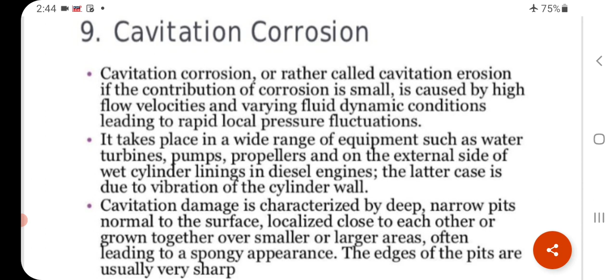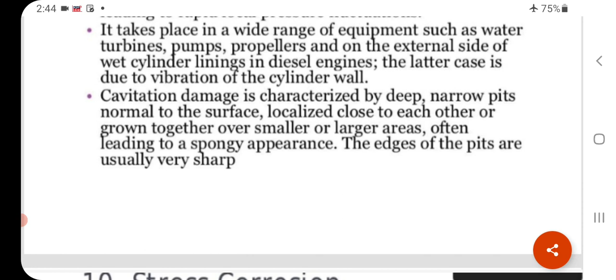Cavitation corrosion, or rather called cavitation erosion, takes place in a wide range of equipment such as water turbines, pumps, and propellers on the external side. Cavitation damage is characterized by deep, narrow pits normal to the surface, localized close to each other, or grown together over smaller or larger areas. The edges of the pits are usually very sharp.